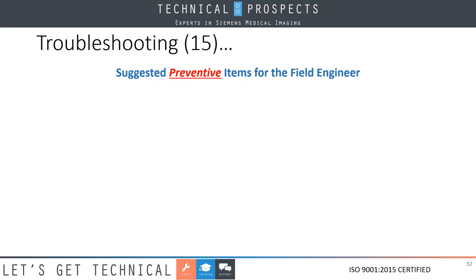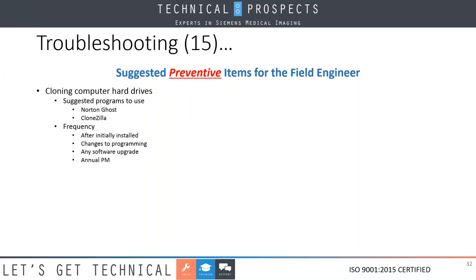So some suggestive preventative items here for you guys as we get near the end of the presentation. Number one, and I would strongly advise this, cloning of your hard drives, all right? I don't care if you use a Norton Ghost, Clonezilla, or if your manufacturer has a specific program. I know Siemens recommends Cobra, all right? For example, when do I want you to clone these hard drives? Once the machine is initially done, all right? If there's any changes to programming, if there's a software upgrade, and at the end of the annual PM that you do, so that if something happens to your hard drive, you can quickly get yourself back up to speed.